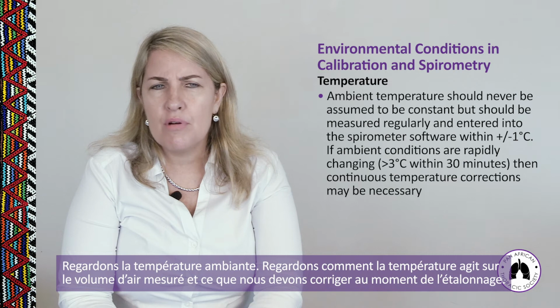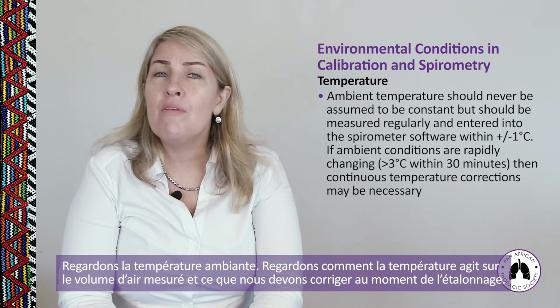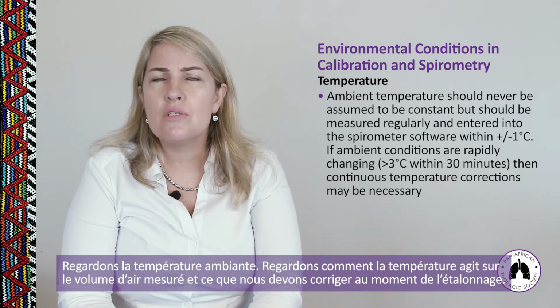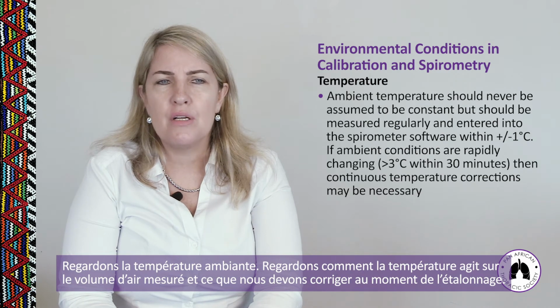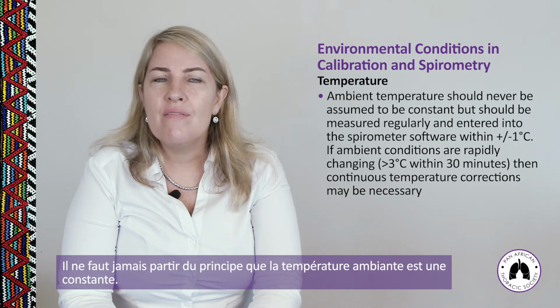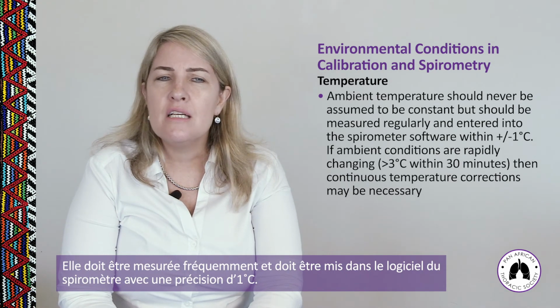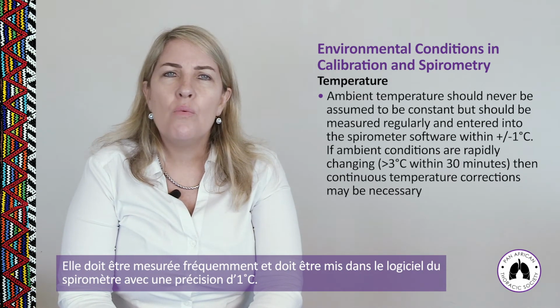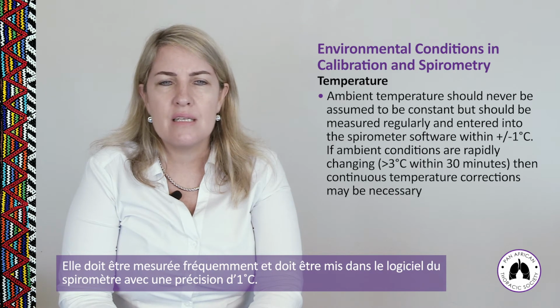Let's look at how temperature affects the volume of air measured and what corrections we need to make at the time of calibration. So the ambient temperature should never be assumed to be constant. It should be measured regularly and entered into the spirometer software within plus or minus 1 degree Celsius.